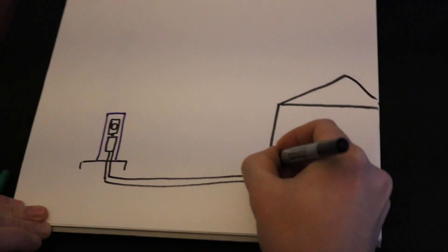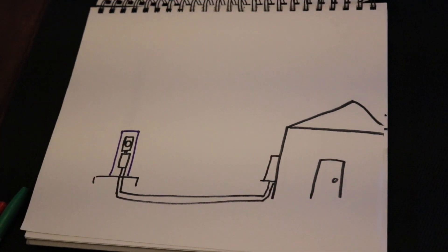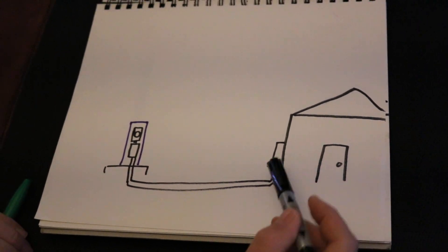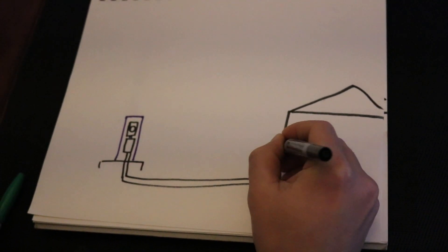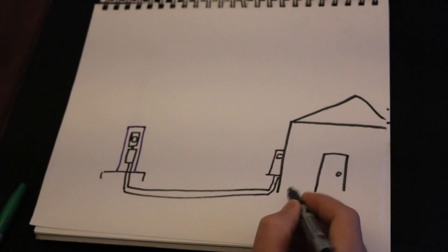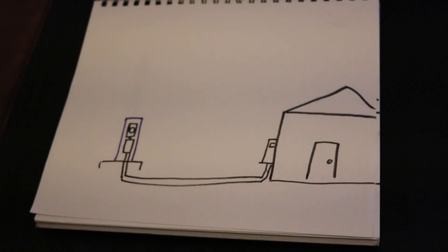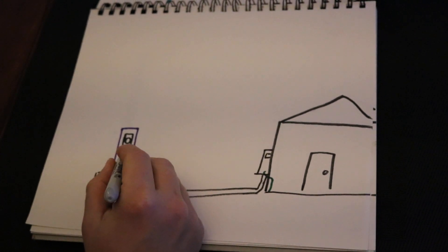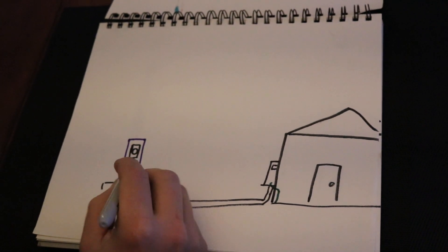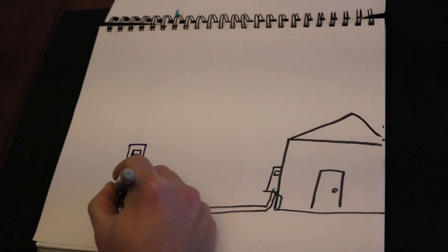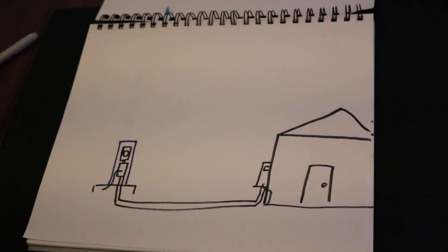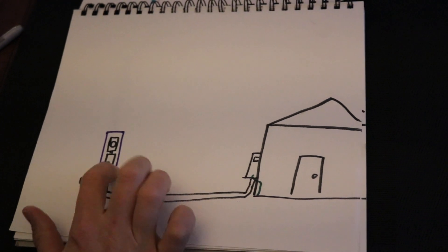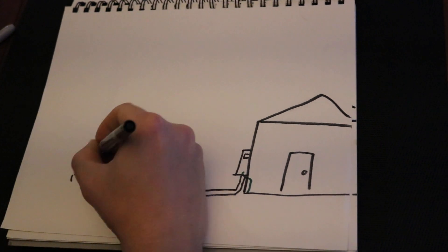You have your meter on the pedestal, a disconnect, and out of this disconnect you'll have an underground conduit that will run over to the house here. This will actually technically be a sub panel. Here in Austin they require anytime you have a separate structure that there be a disconnect regardless that it is a sub panel. So if I were doing this I would have a main breaker here just as a safety switch disconnect. Anytime you have a separate structure you're required to have a ground. Say this is a slab, this would be a Ufer or it could be ground rods. I've seen a lot of these pedestals where I live in the Central Texas area, PEC, and I've seen a lot of them that don't have a ground rod. But you should have a Ufer ground here as well.